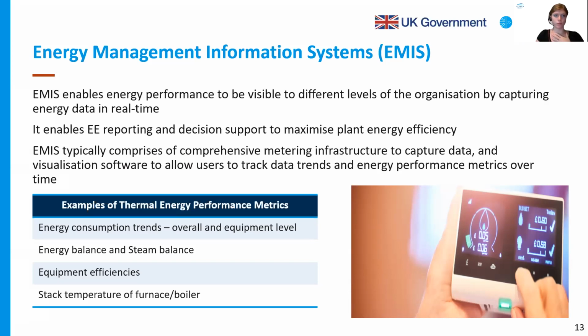So when an energy performance parameter is out of range, that also means that the equipment's performance parameter is out of range. So energy and equipment performance could go hand in hand. That could trigger potential equipment fault detection. When is the next maintenance to be triggered? The maintenance team can also get a better understanding of the mean time to failure, so that they can schedule their repair time accordingly. So it also helps schedule maintenance as well.